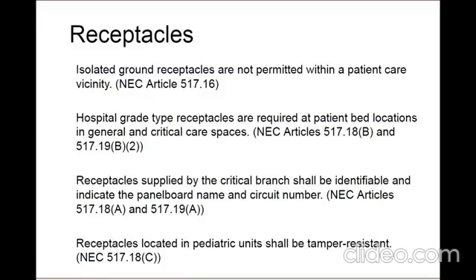Hospital-grade receptacles are similar to general use receptacles, except they include increased grounding reliability, assembly integrity, strength, and durability. If you have ever used an old receptacle with fatigued contact tension, you would understand the concern when the equipment supplied by the receptacle may be supporting life support equipment. NEC 517.18(B) and 517.19(B)(2) require hospital-grade receptacles at the patient bed location.